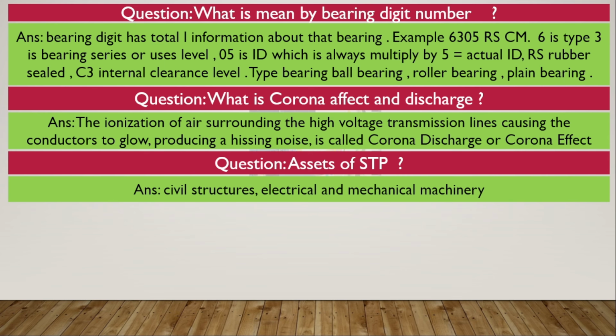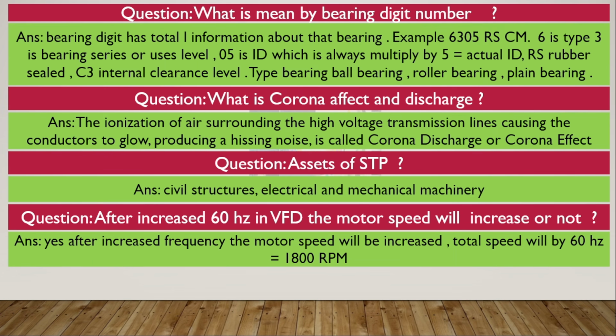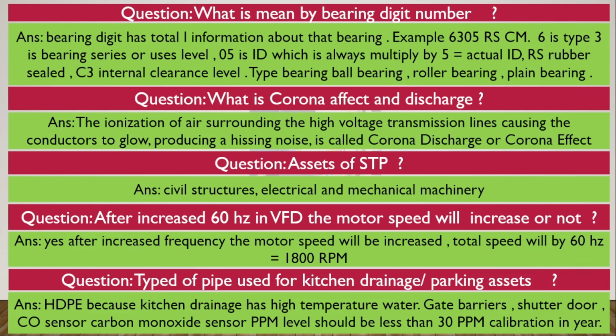Assets of STP: civil structure, electrical and mechanical machinery. After increasing to 60 Hz in a VFD, will the motor speed increase or not? Yes, after increasing the frequency, the motor speed will increase. Total speed at 60 Hz is 1800 RPM. What type of pipe is used for kitchen drain, and parking assets? HDPE, high density pipe, because kitchen drainage has high temperature water. Parking assets are the gate barrier, shutter door, and CO sensor, carbon monoxide sensor. The ppm level should be less than 30 ppm. Calibration is required every year.